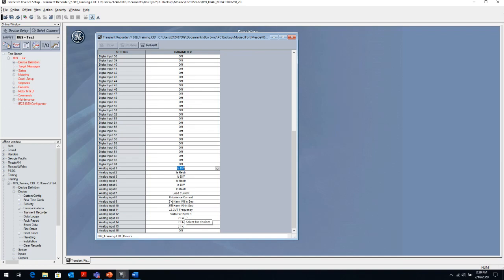In my case here, if this is a differential relay, I want to look at the differential currents and restraint currents that the relay is calculating, or I want to look at the third harmonic voltage that the relay is measuring, right? Because if we're doing a third harmonic voltage element, we want to see what the voltage difference is. We might see the unbalanced currents that the relay is calculating, and so on and so forth.